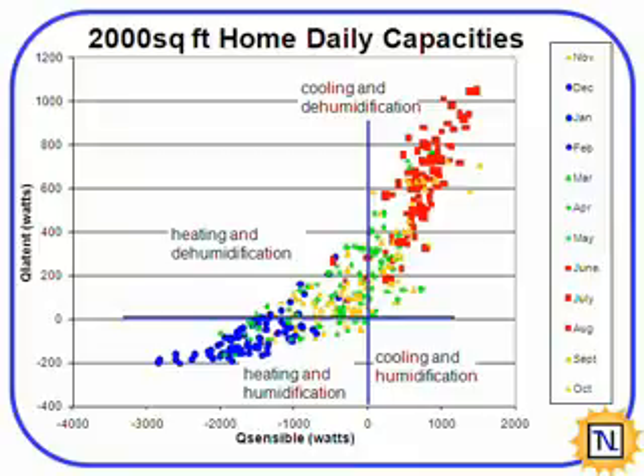And you can see for Illinois, we just have the extreme. We have the worst of the worst. We have hot and humid weather in the summertime and extremely cold weather in the wintertime. But what you also see here is that the loads are relatively small for this type of house construction, an energy efficient house. This is our cooling load, actually, which will need from 1 to 2,000 watts.